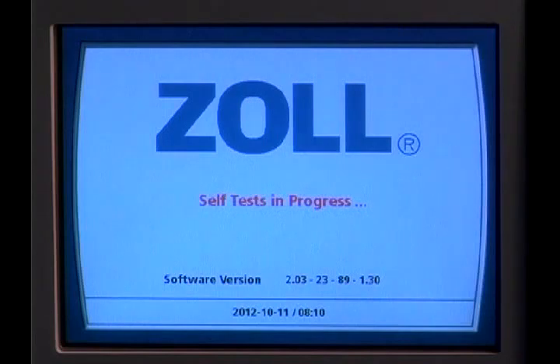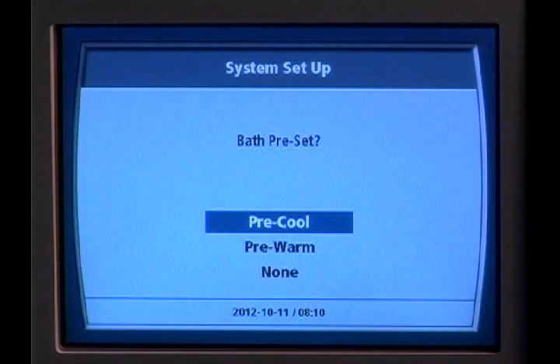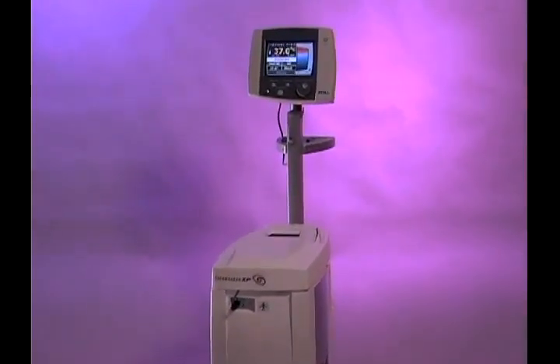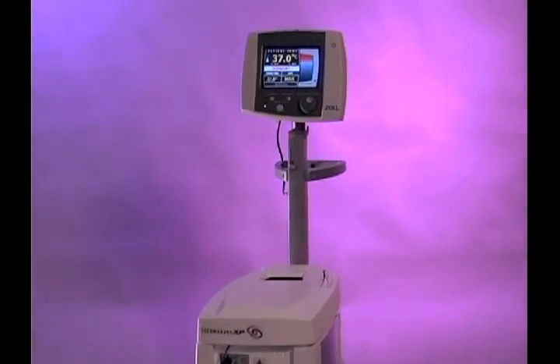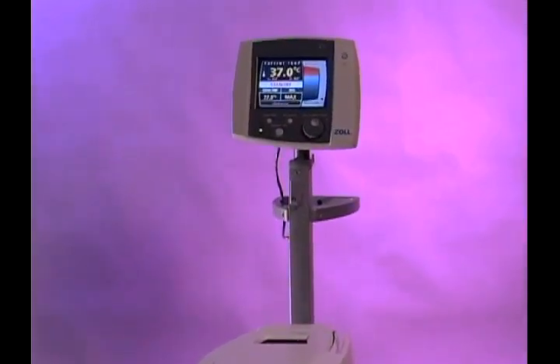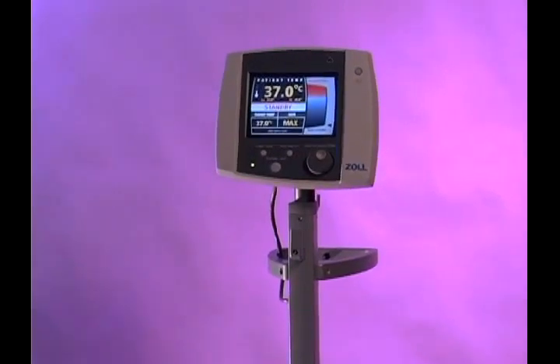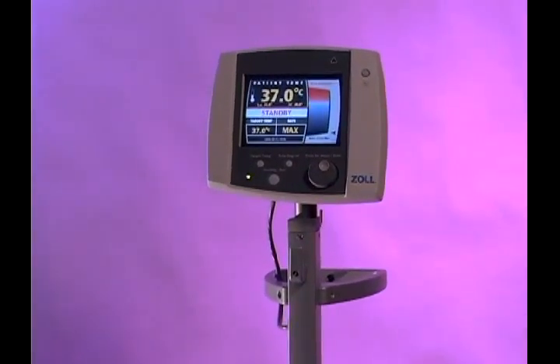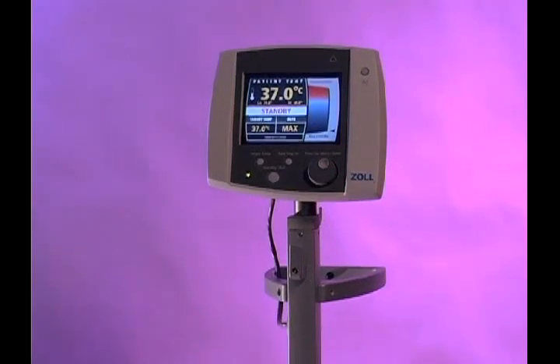Following a 10-second self-test period, the first question asks if you wish to pre-cool or pre-warm the system. For optimal results, it's very important that you begin pre-cooling or pre-warming the system at least 20 minutes before connecting the system to your patient. This ensures that the saline temperature is set at the appropriate minimum or maximum temperature extreme required when you are ready to connect the patient.